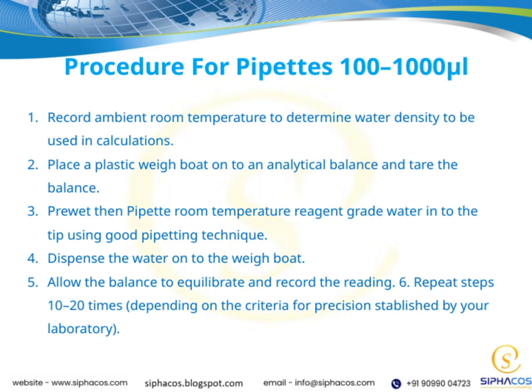Once you've pipetted the water, dispense it onto the weigh boat. Allow the balance to stabilize or equilibrate, and then record the weight reading. It's good practice to repeat this process multiple times, typically between 10 and 20 times, depending on the precision criteria established by your laboratory. Repetition helps ensure your measurements are reliable and consistent. By following these steps carefully, you'll improve the accuracy of your pipetting technique, which is essential for precise laboratory work and valid experimental results.